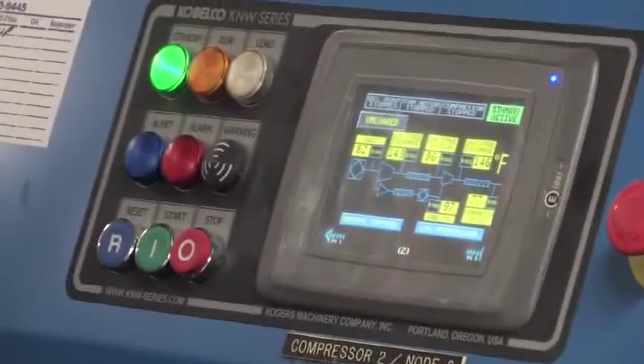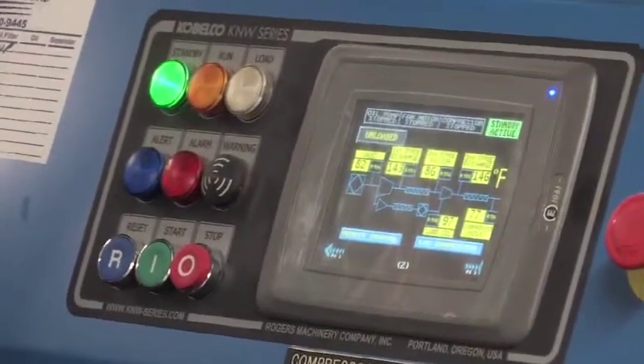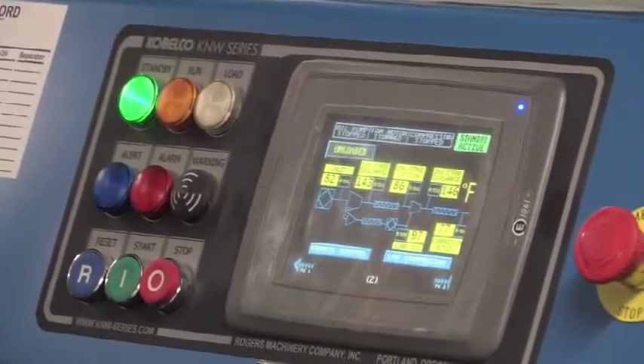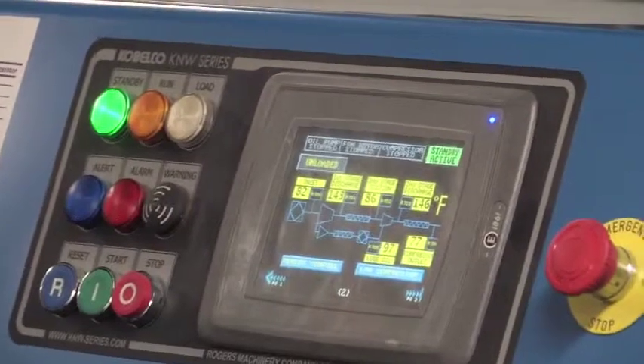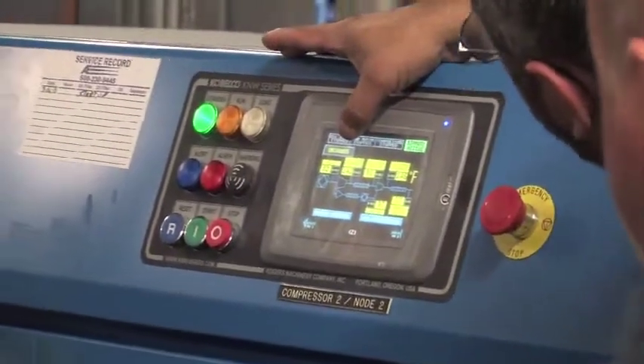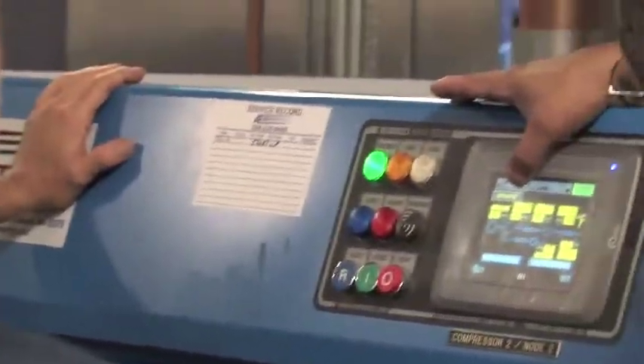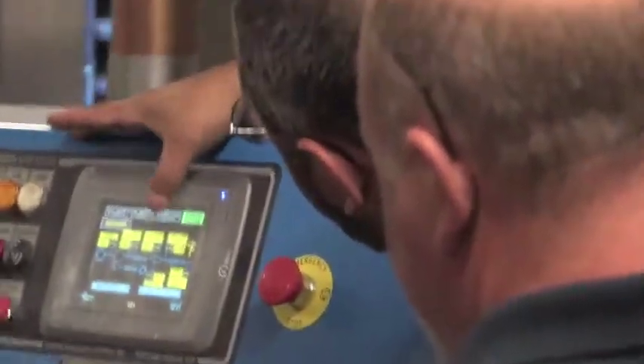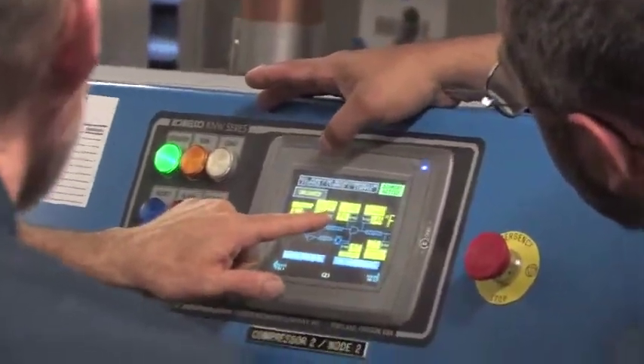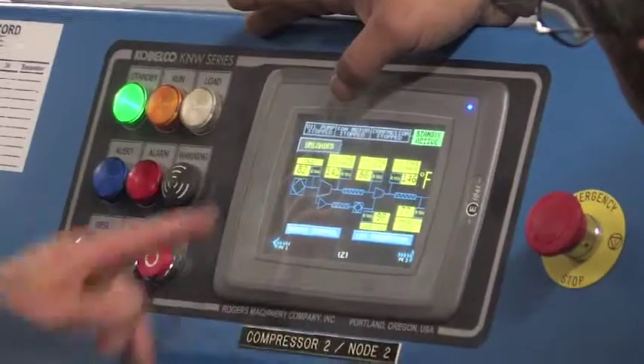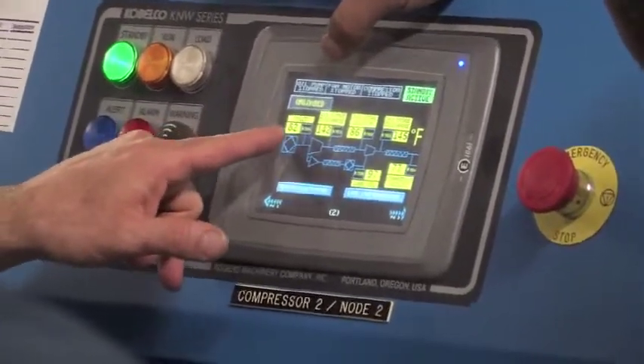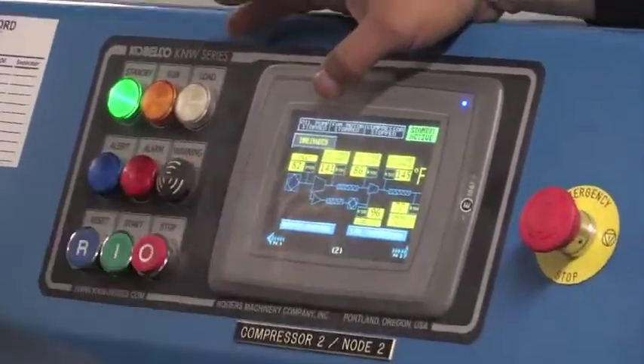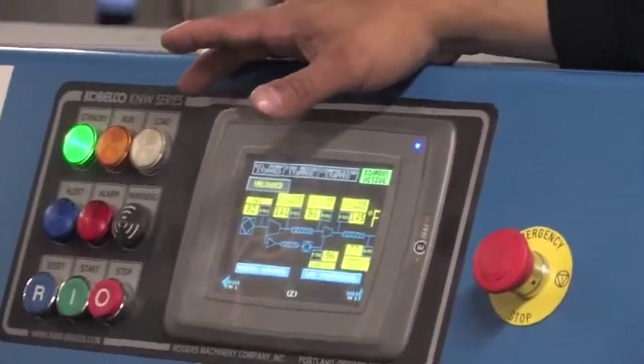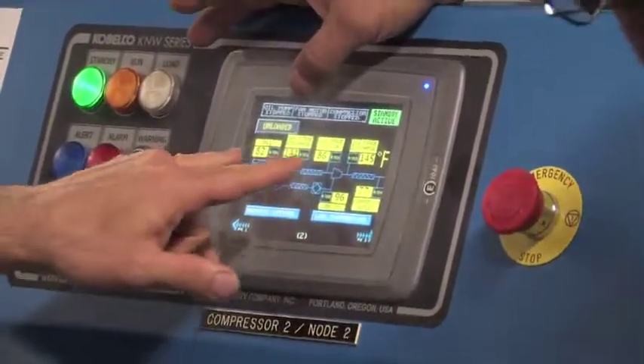All right, and our temperatures. So we have, now that's a new one too, an inlet temperature that's displayed. Oh, okay. So now you get something that tells you what the air coming in is. And first stage discharge, second stage inlet. That tells you your interstage cooler is working real well. Your first stage cooler, because it's bringing in an 82, it's heating up to 142. Yep, it's putting it almost within 5 degrees. Is that what it's supposed to be, within 5 degrees?